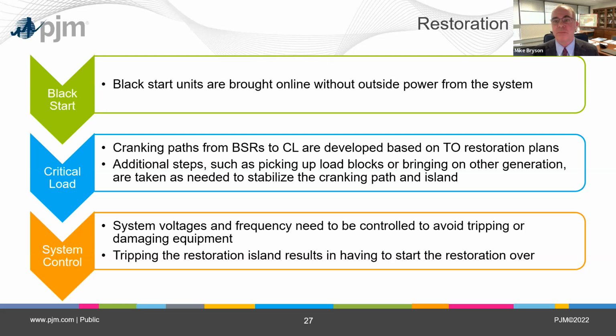One of the critical parts here is picking up pieces of load along the way that help balance the system. Paul touched on this too. It's really critical that the whole time you're restoring the system that you balance the load and generation, because if we get this wrong, we start all over again. And it's kind of a tricky thing, a lot of manual switching out in the field with a lot of utility crews.